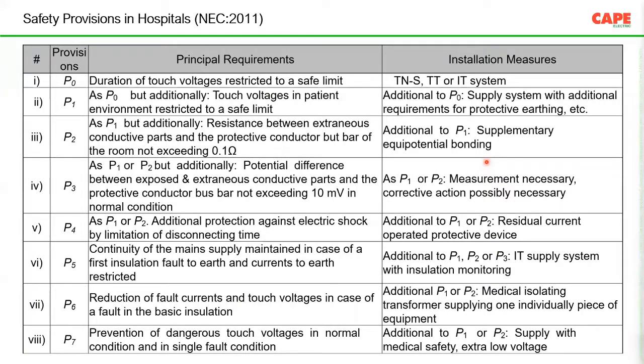Now, the National Electrical Code 2011 also gives you some indication of the kind of protective provisions required in a hospital, in a medical location. However, NEC 2011 will be replaced by probably an NEC 2022 within 2-3 months. But I would recommend that the provisions of NEC 2011 can also be followed, because detailed information is provided. Different safety provisions are recommended in the standard, starting with P0, P1, P2, P3, P4, P6. You can see it here, different provisions, and the explanations are provided.